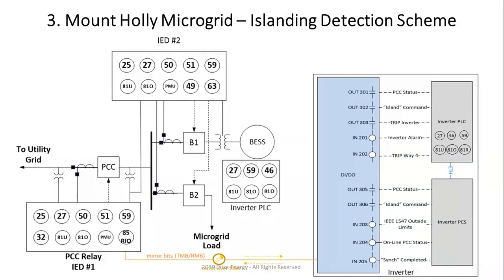So essentially what we do is, if you see this output 306, that is the output that we close when PCC senses the islanding condition to tell the PCS to go to the island, and then the PCS does the switching, right? We also tell the island command on the output 302 on the top to the inverter PLC. The reason we do that is, if the inverter PLC does not issue a command to the PCS, because that's how it's typically always done, then we need to tell the PLC that we have issued a command on our own, right? So that's the reason why we have the same thing on top and the bottom.